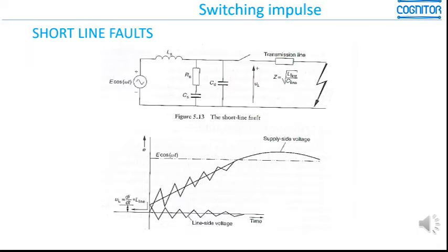In this case, the combination of these values and the reflection of the waves can lead to a wave shape more or less like the one that I show in the figure, and these very fast transients can be bad for the circuit breaker, and can prevent it from breaking the current correctly if it's not designed for this circumstance.